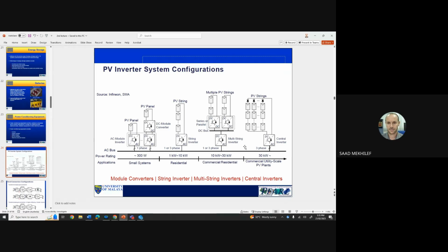But as I said, in terms of cost effectiveness this is the best choice, because we usually measure it as dollar per kilowatt. So you'll find that central inverters have the lower cost, and string and multi-string inverters fall somewhere in between the micro inverters and the central inverters - not too big and not too small, meaning they try to match between the two.